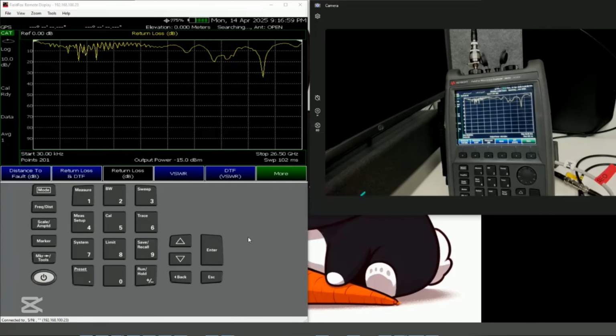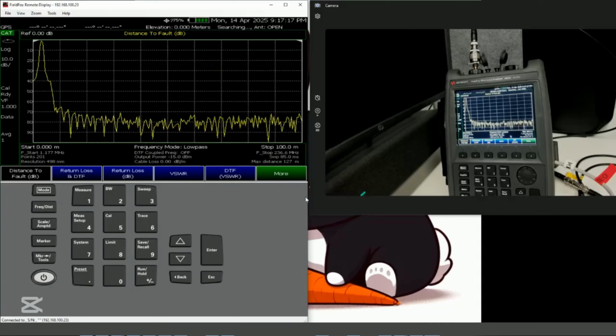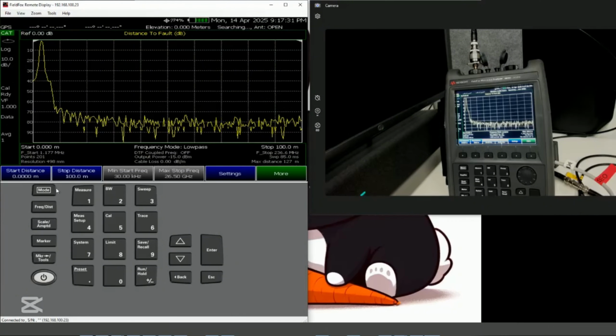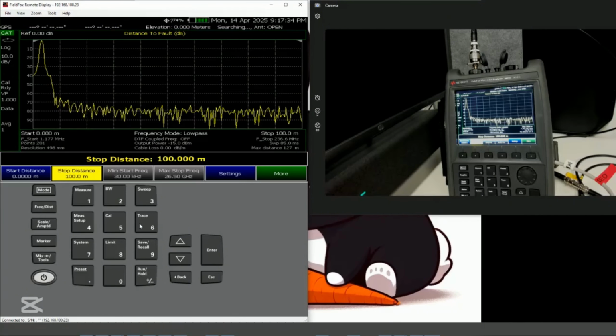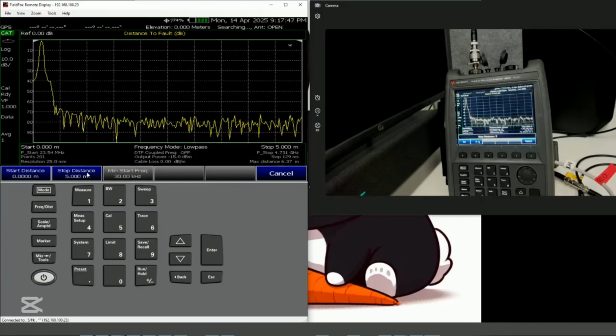So I really start from scratch, and let's go to preset factory, mode, CAT, which is cable antenna test. I don't really have GPS, it doesn't really matter, and I will go straight to measure, distance to fault. Because both cables added together are about 2 meters in physical length, I'll set the start stop to something shorter than 100 meters. Let's go to frequency. For stop distance, because it's 2 meters, we can add in some buffer because we want to see where the open end is. So I'll stop at about 5 meters. It's up to you, you can play around with that.